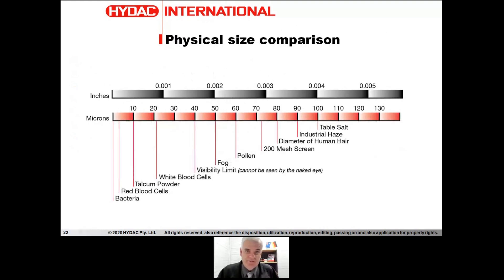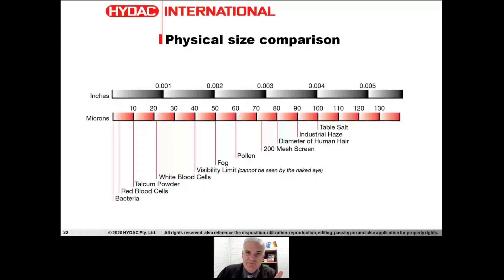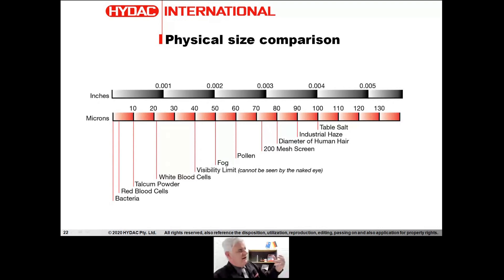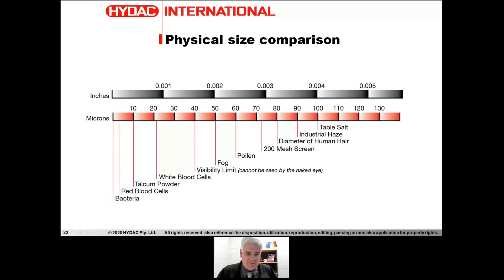We can't ignore the physical size of contaminants. This chart from a HYDAC catalogue from the USA shows that the visibility limit is around 50 microns — and that's for someone with perfect vision. Anything under that you can't see with the naked eye; you'd need a microscope. Yet 50 microns is a massive size contaminant for these systems. If I asked what size filters you use, people typically say 10 microns — that's one fifth of what you can see. So you can hold up a sample of fluid, think it looks clean, and be completely wrong.